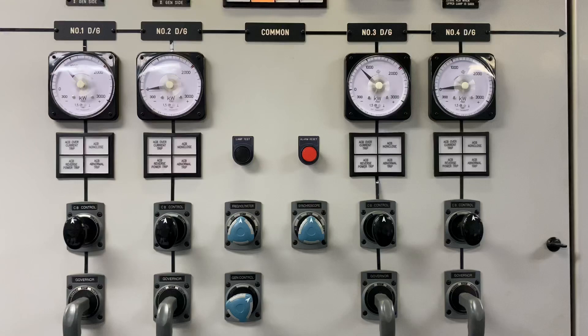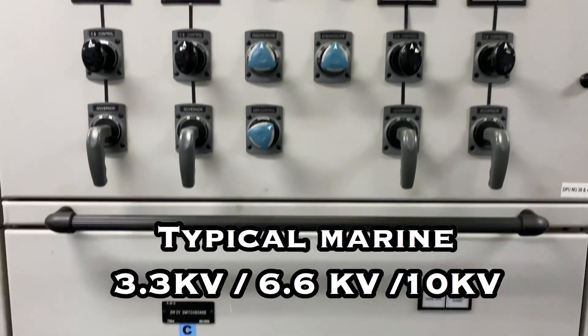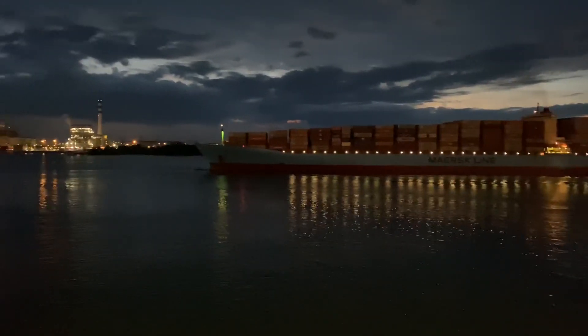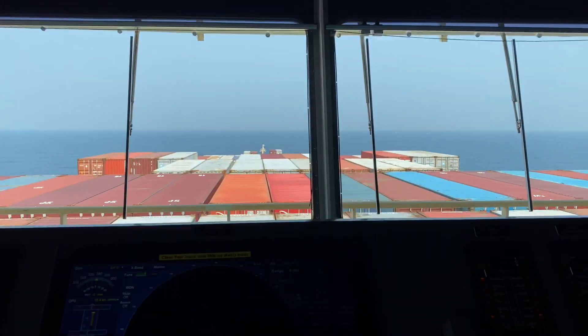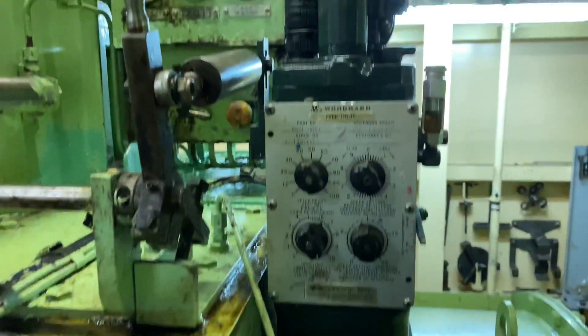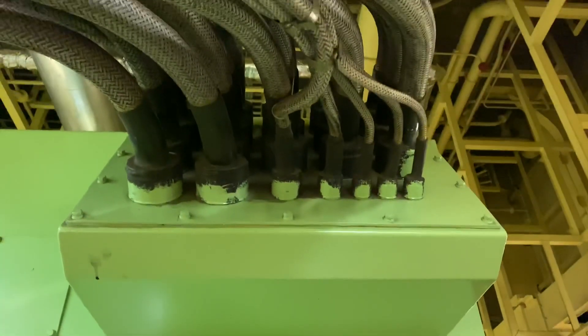Typical marine high voltage systems operate usually at 3.3 kilovolts, 6.6 kilovolts, or 10 kilovolts. The higher the load you will have in a vessel, the higher ampacity you will need in your conductors or wires. That means the required diameter for the wires will also get bigger. The ratings on the circuit breakers, fuses, conductors, bus bars, and other electrical components will also increase in order to accommodate such high loads.